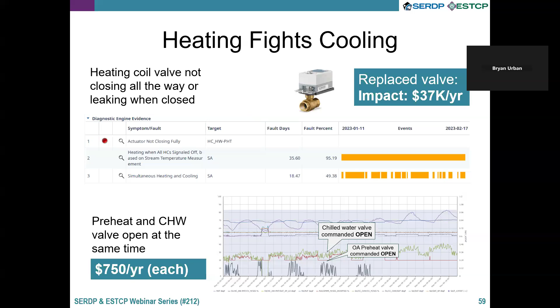Replacing that valve could save about 40 grand a year. And on the bottom, it's another example where a preheat and a chilled water valve were opening at the same time for a certain amount of the time. And so again, you're heating and cooling at the same time and wasting potentially $1,000 a year each time that happens. So again, things you would never detect, nobody would report it, but are wasting energy behind the scenes.